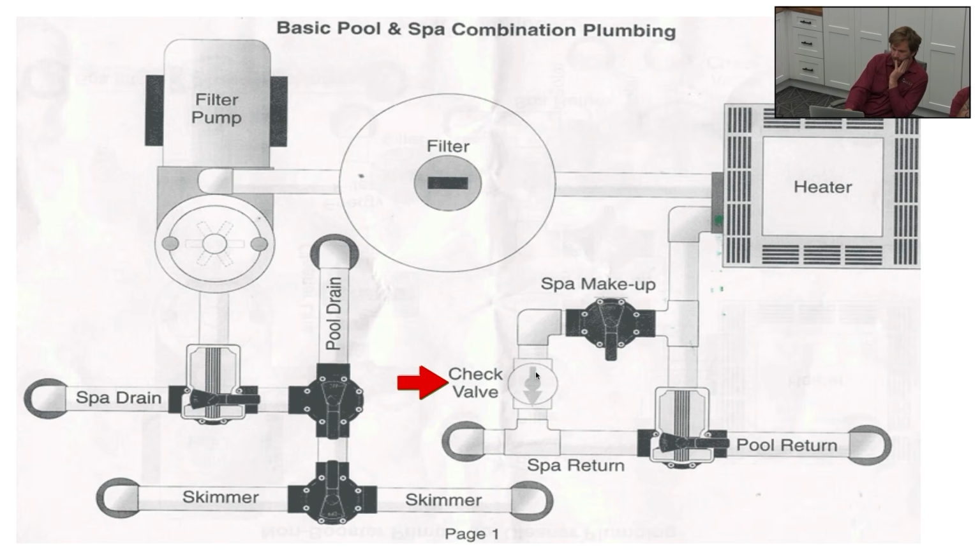This shows a check valve in place. There's often a check valve if you don't have the Hartford loop, you have a check valve option. And if you guys see that, it's a little clear sight glass, and inside of it is a spring-loaded damper. Sometimes the spring will break, or it'll get clogged, and it will be creating your water flow issues.